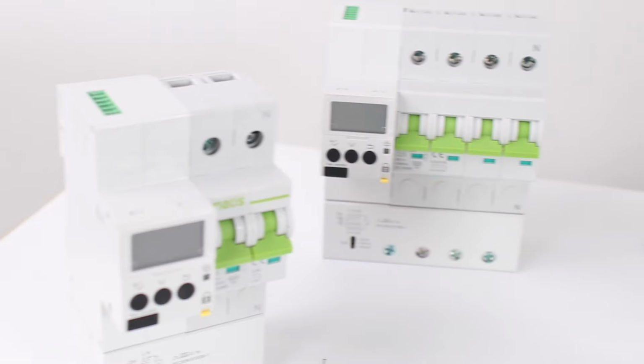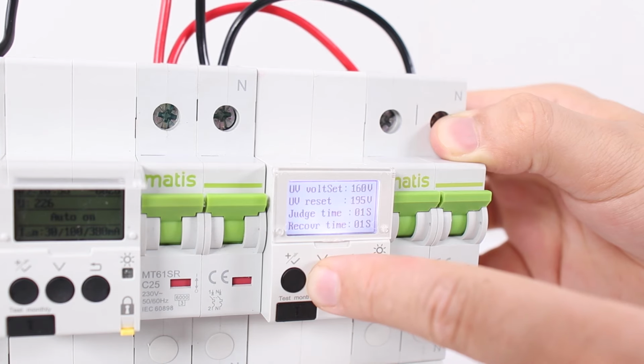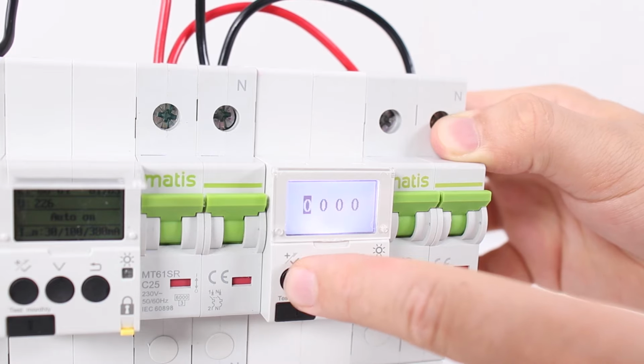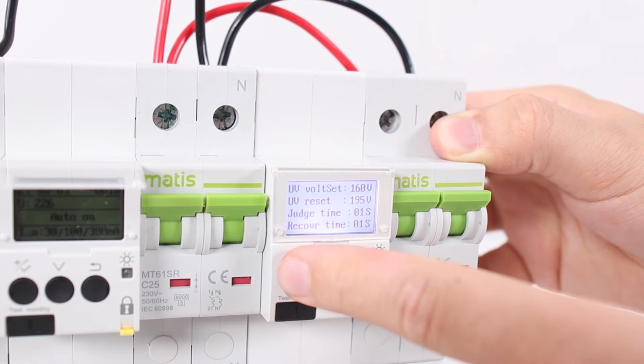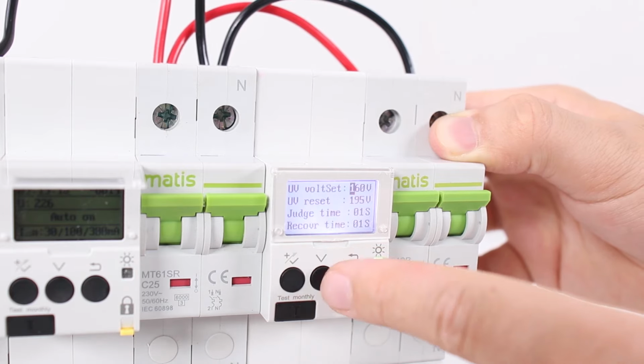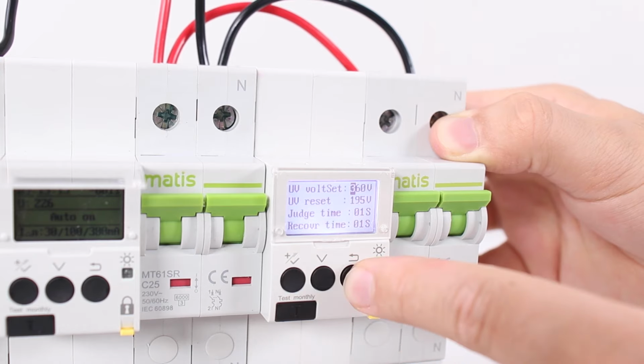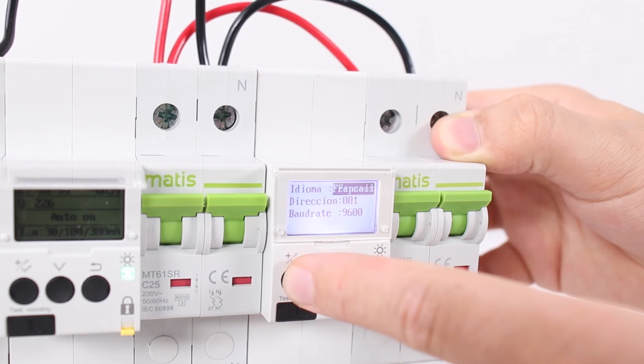The check time can be changed both in the software and manually via the control panel in the device and the LCD display that is located on the front side of the device. They are also necessary for operational verification by specialists, since the LCD display shows all the information about voltages, trip history, residual current values, amperage and other data in real time that will help determine the cause of the malfunction. Using the control buttons, you can also change the reswitching operation mode. Change the interface language to English, Arabic, Spanish and French.